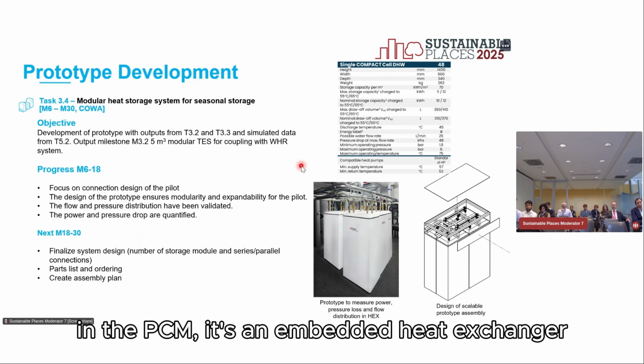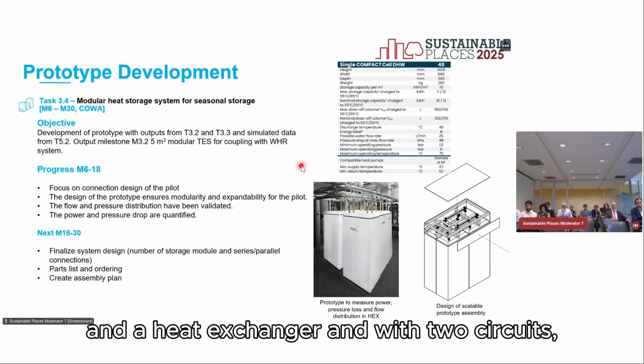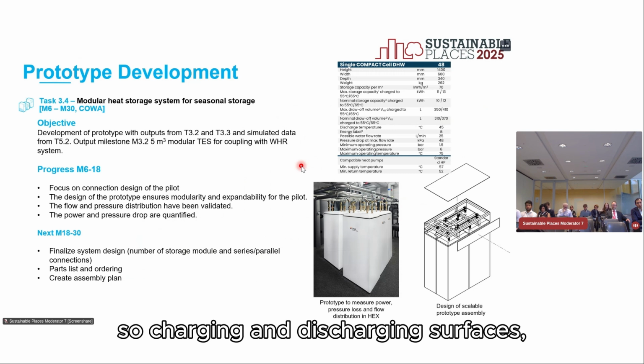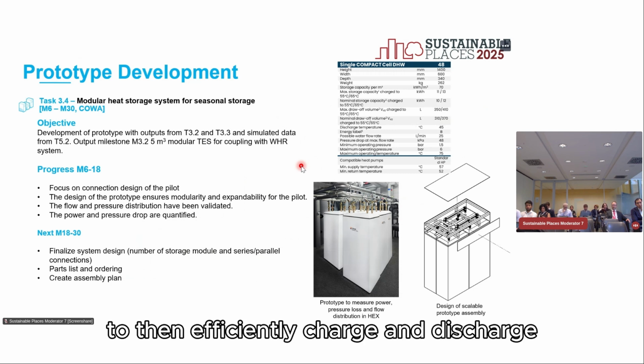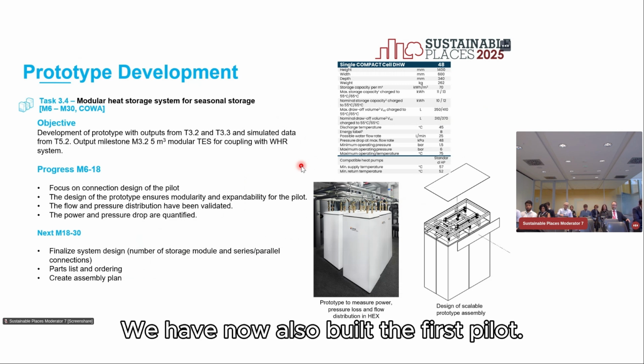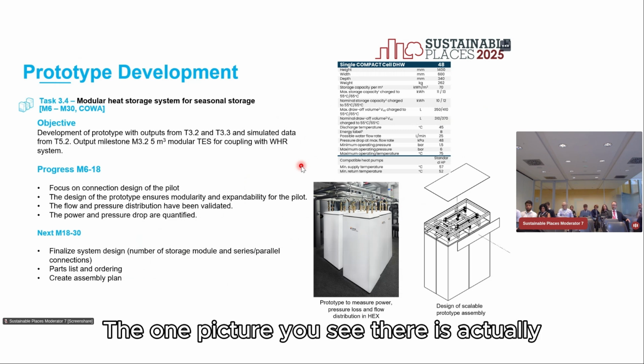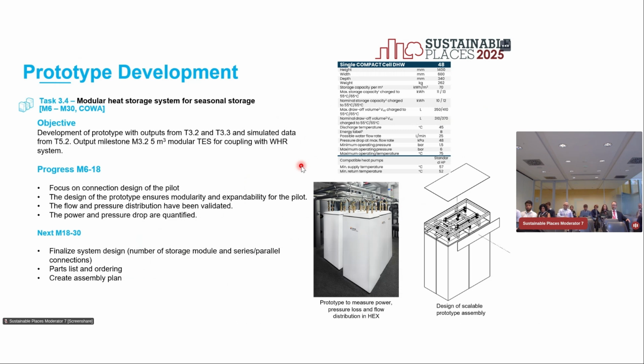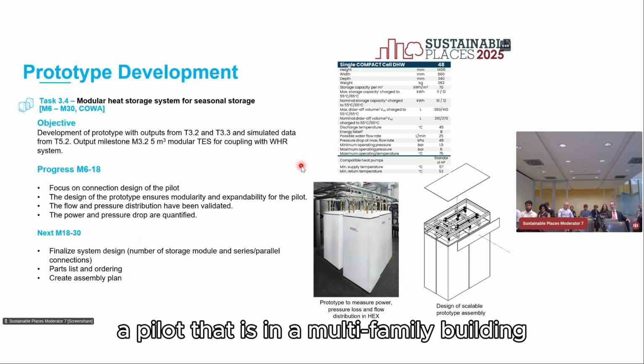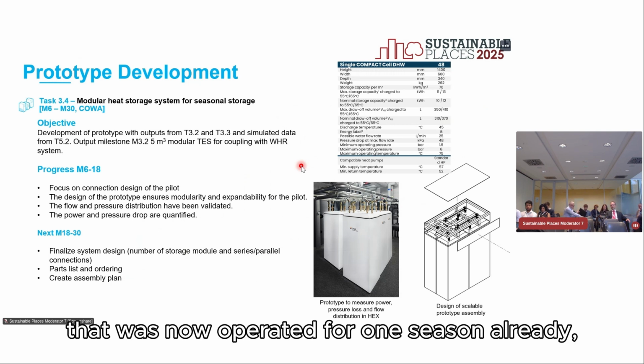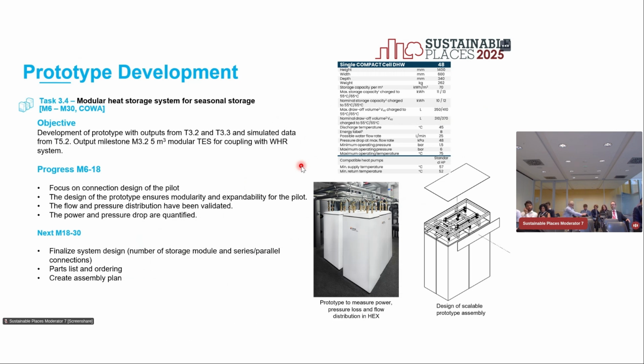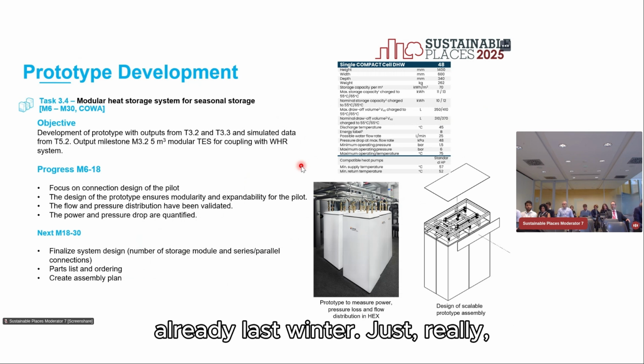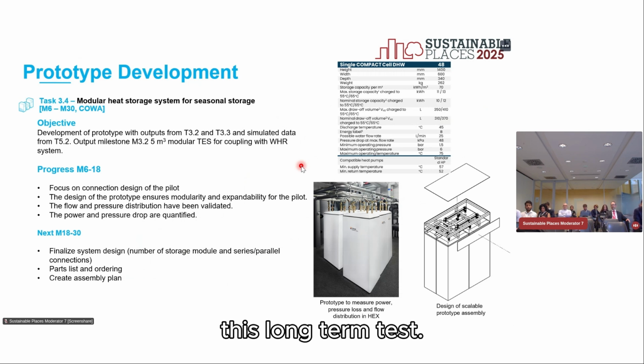In there, in the PCM, it's an embedded heat exchanger, fin heat exchanger, with two circuits, so a charging and discharging circuit, to then efficiently charge and discharge the material. We have now also built the first pilot. The one picture you see there is actually a pilot that is in a multi-family building that was now operated for one heating season already. So it started to operate already last winter, just really this long-term testing.